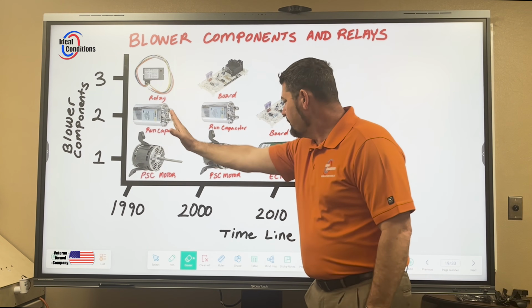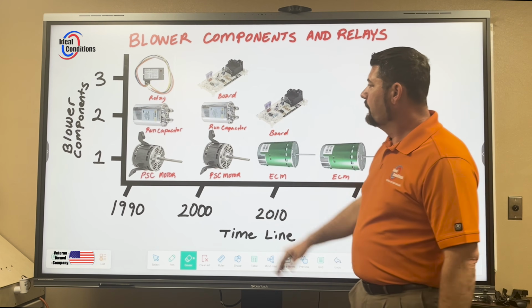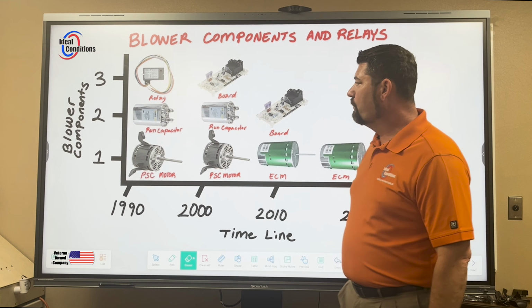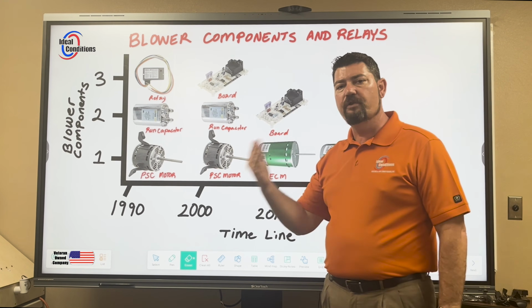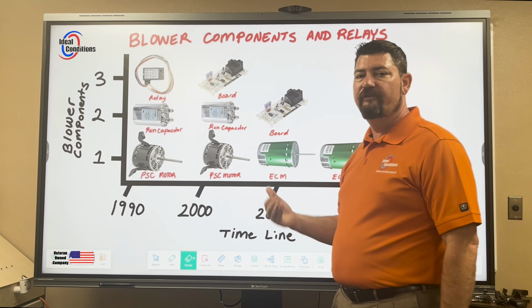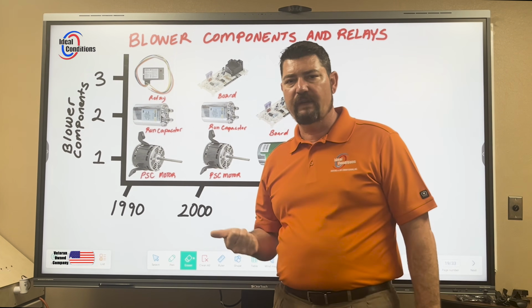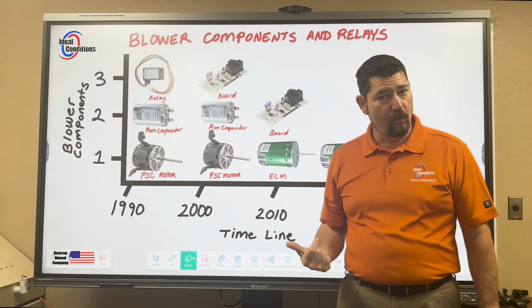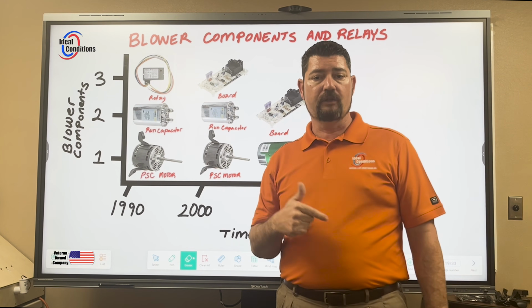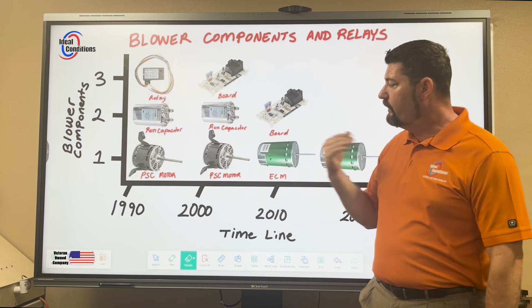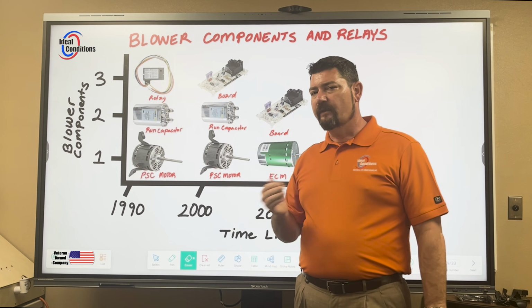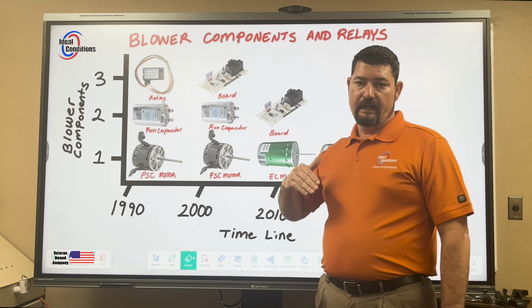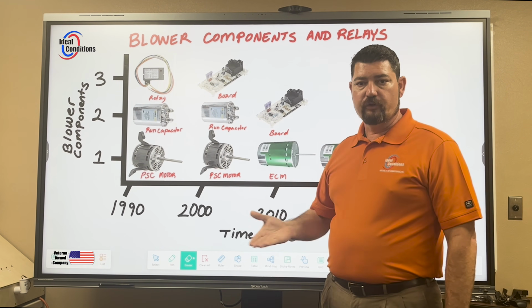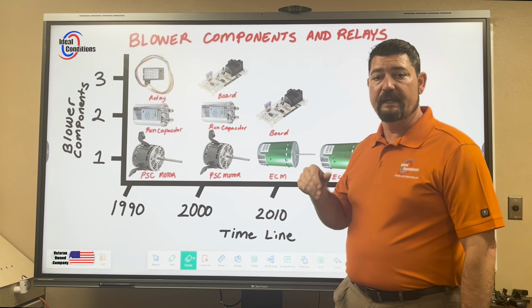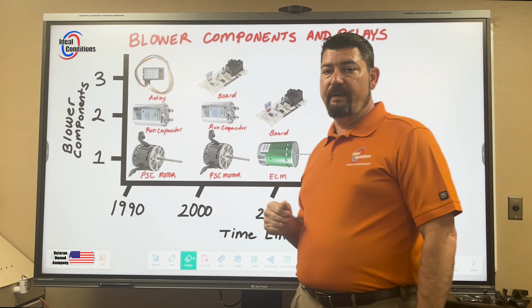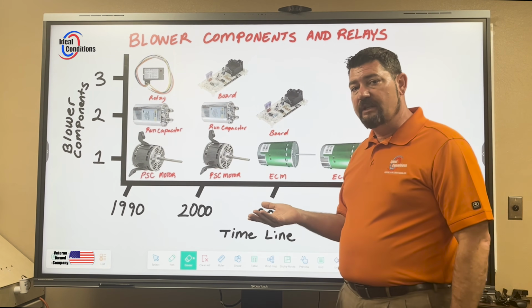And as we progress down this timeline, we started getting into control boards so we can manage time, that on delay or that off delay, so we can get more efficiency out of our evaporator coils. Those evaporator coils, they get cold, they get warm. They get warm when they're in heat mode, they get cold when they're in cool mode. And so if we can delay just for a little bit on that on time, we can get more comfort out of our motors when they first start to move air across those coils, getting more heat or more cooling capacity out of it with extra dehumidification.